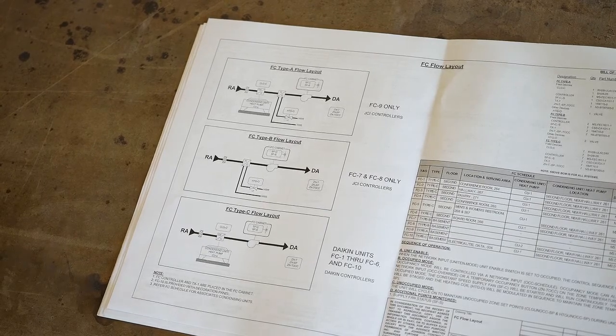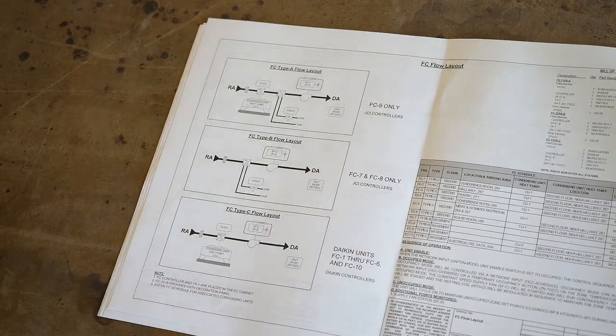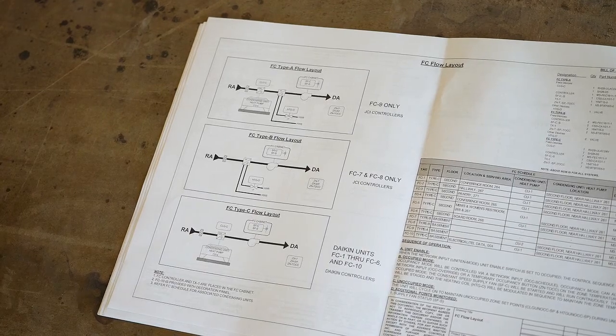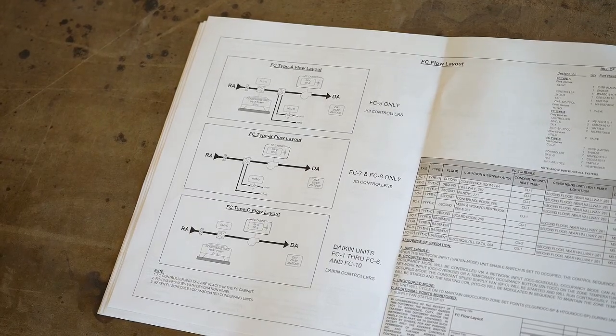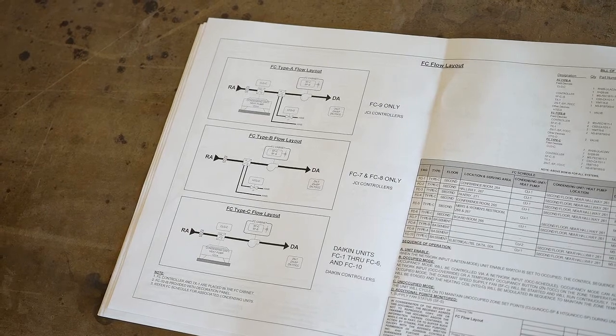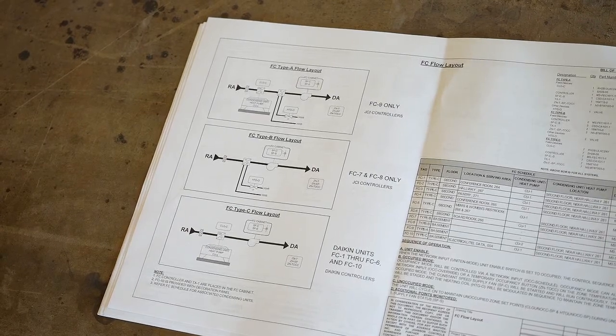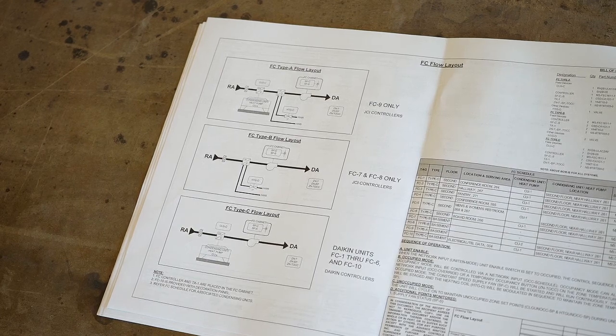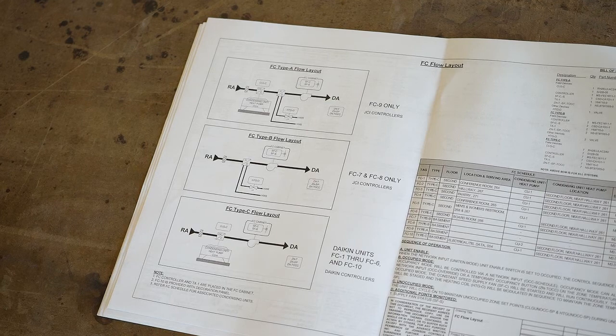Okay. So we'll just touch on these Daikin units just a little bit. We're basically not controlling anything on the Daikin units. We're pulling the points into the front end so that they can be monitored, and we're generating a few alarms if the temperature gets way off set point. The way the Daikin units work is you have 2 condensing units outside. You have basically a master and a slave, and those are daisy chained together. And then that trunk coming off the master unit goes through and it daisy chains to every one of the Daikin units. Okay?